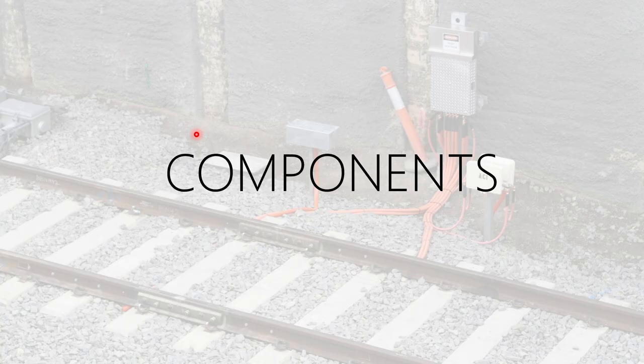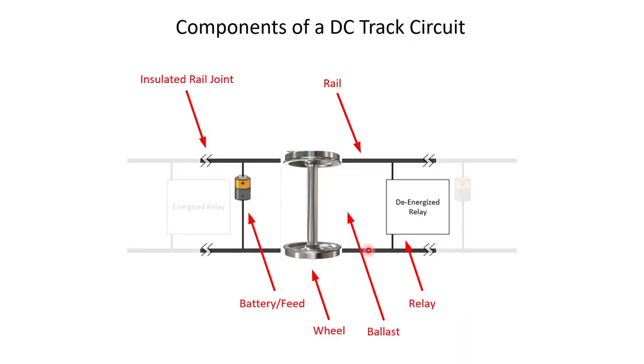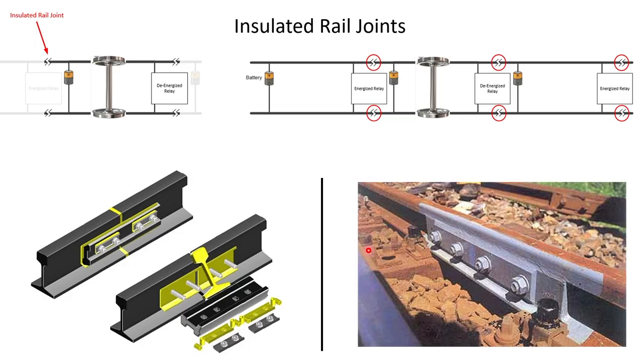Now let's look at all the components of a DC track circuit. The first component is the insulated rail joint. What the insulated rail joint does is electrically isolate one circuit from the other — when you have a circuit with a battery and an energized relay, you want it electrically isolated from the next or previous circuit. Without this separation, you could have interference or unwanted supply energizing the relay, and we want an isolated circuit.